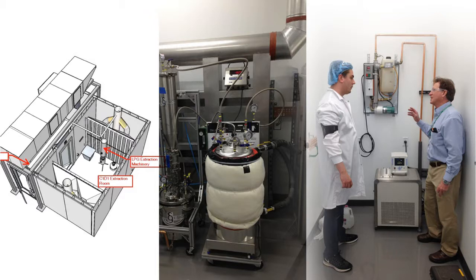Part of the ante room is classified as Class 1, Division 2. Part of the ante room is not classified, so that's your entry and exit point. And then you move into the actual extraction room, which is the NEC Class 1, Division 1 room, and that's where you'll have your extraction equipment. In that particular room, you'll have dedicated ventilation.